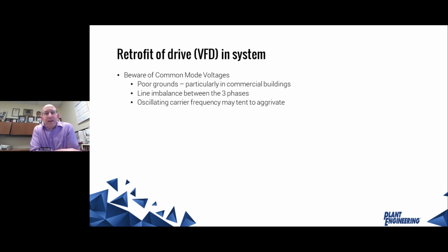A few other things to take a look at when you're putting a VFD into the system: there are these things called common mode voltages. I'm not going to get into a lot of detail of why a VFD creates a common mode voltage. Just trust me, it does. And there are some things that we can do in the system to make sure that the common mode voltage does not affect the motor or the system very much.